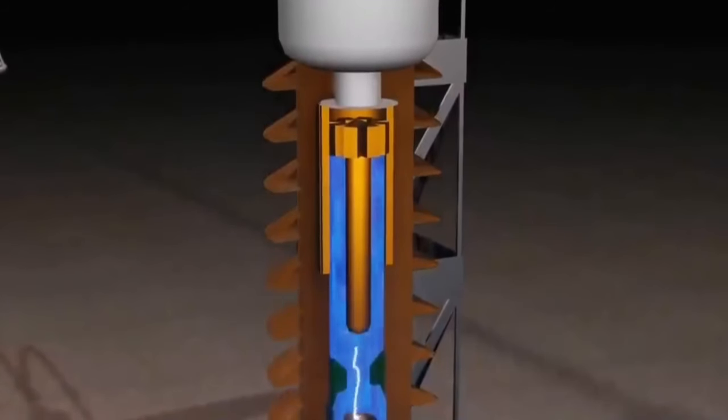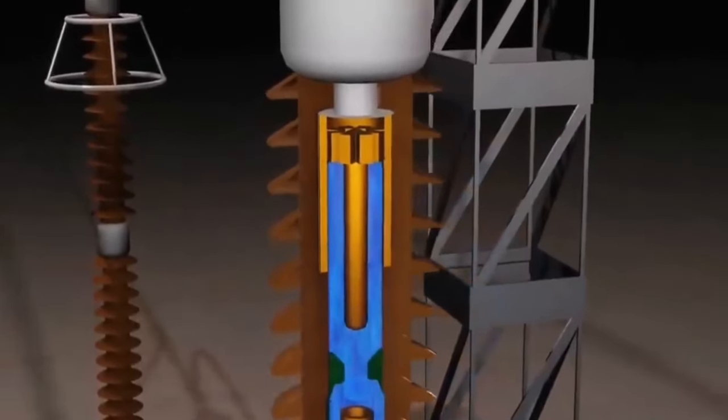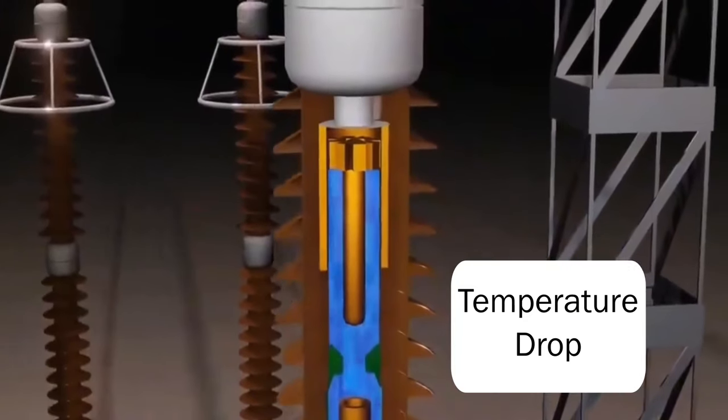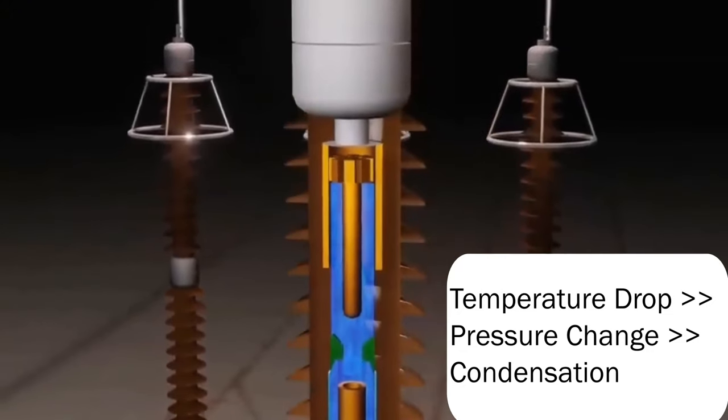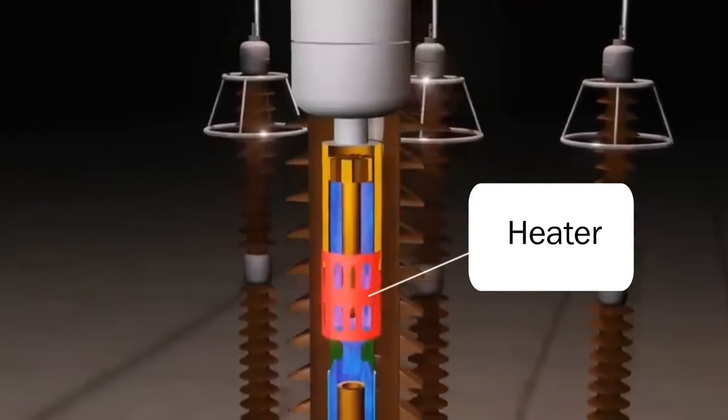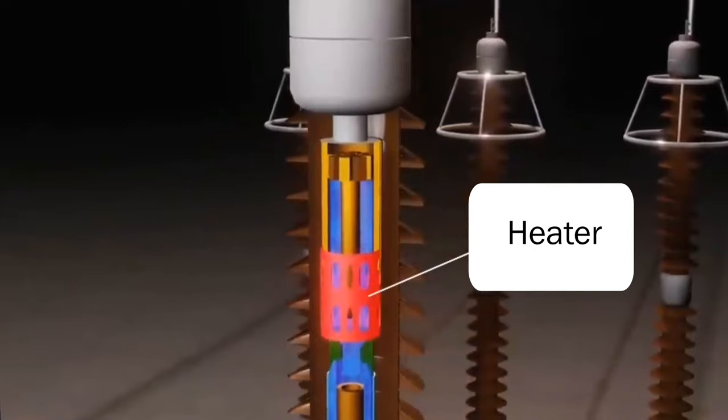However, there is an issue. After the arc is extinguished, the temperature inside the circuit breaker decreases, and under certain pressure, sulfur hexafluoride will transform into a liquid. At this position, a heater is also needed to ensure that SF6 remains in a gaseous state.